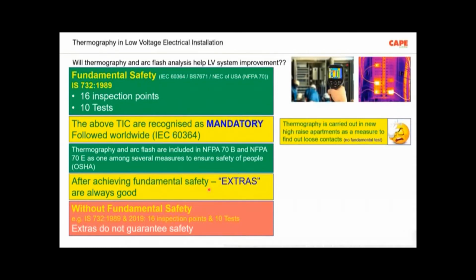So they are not doing any of the fundamental safety measures. I would say 90% of the fundamental safety measures are missing. But finally, a thermography for the wires which are enclosed inside the conduit is made. This is really not at all acceptable. You are violating the basic requirements.